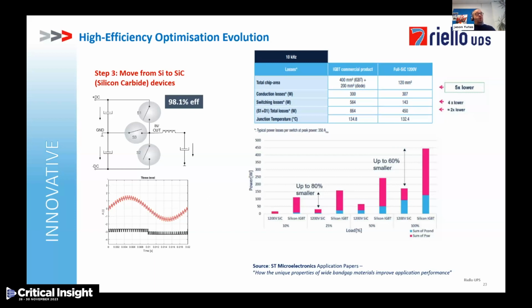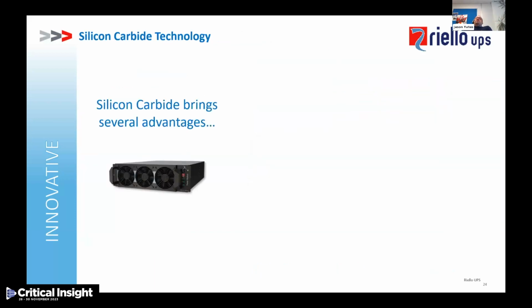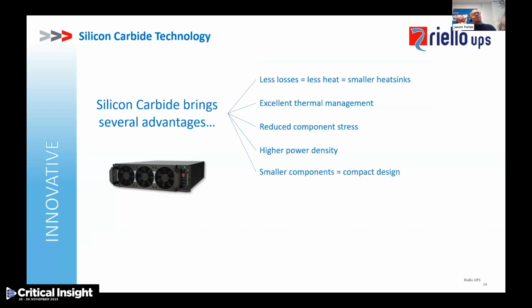Also, the junction temperature can run cooler as well. The graph at the bottom is showing a comparison between 4 different load levels: 10%, 25%, 50%, and 100%. And as you can see, the silicon carbide devices outperform the traditional IGBT in all areas. So it's not just a particular sweet spot. So what is it that silicon carbide can bring to the party? Well, what we can say is there are less losses. That produces less heat. That requires smaller heat sinks. The systems become smaller. They have excellent thermal management. This reduces component stresses.